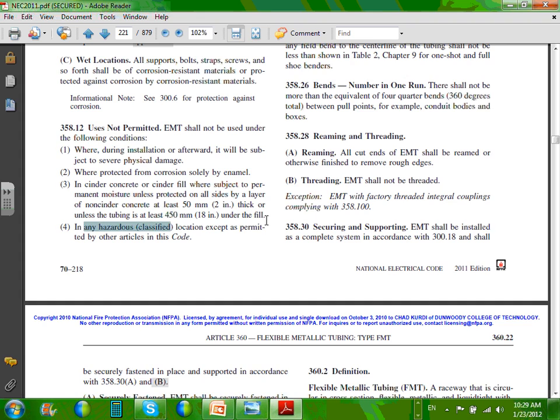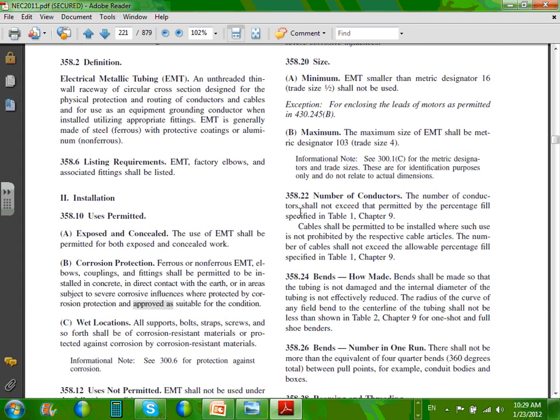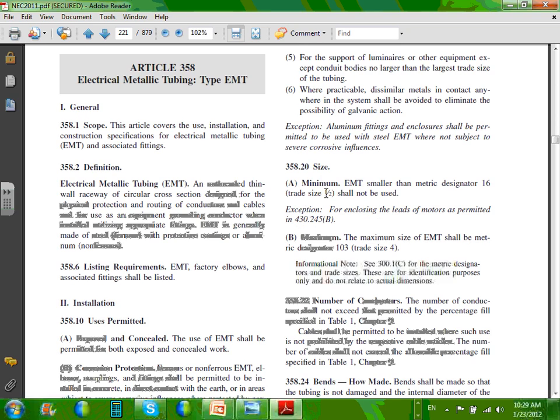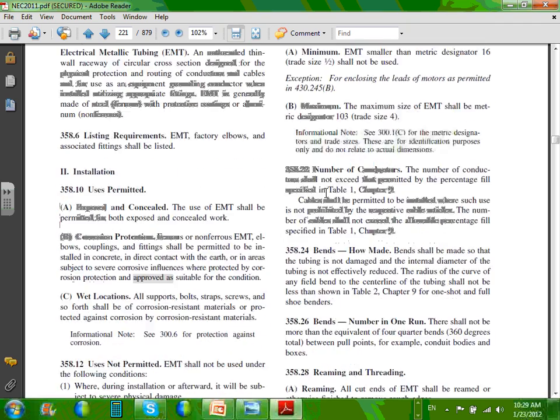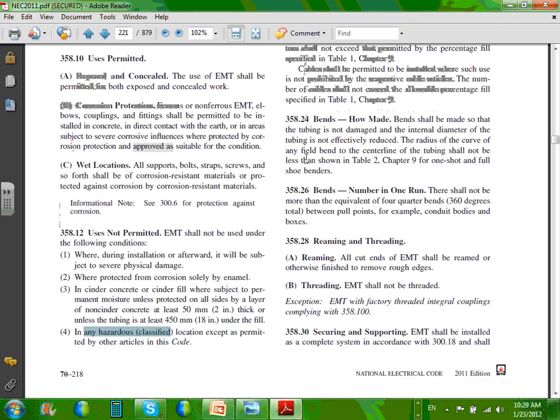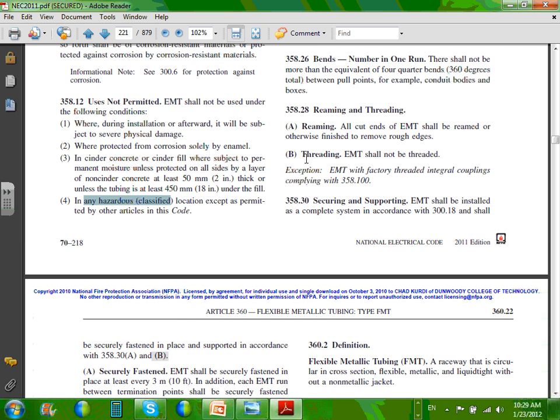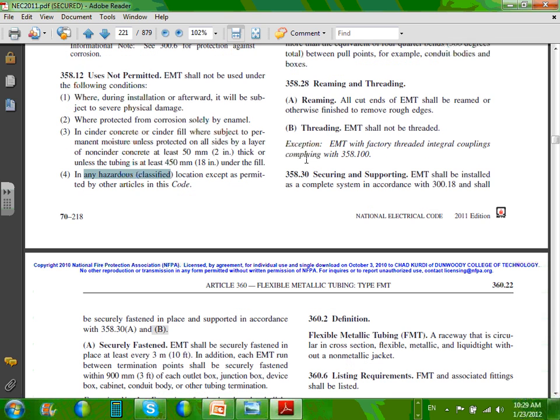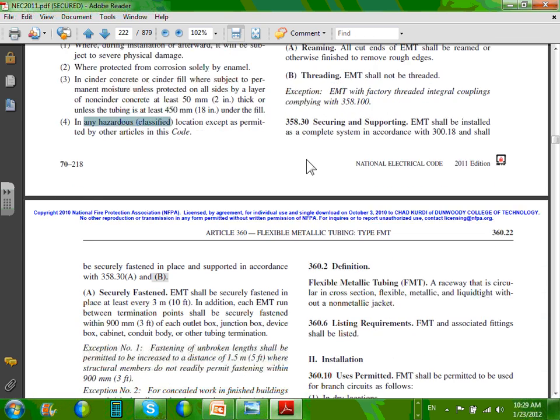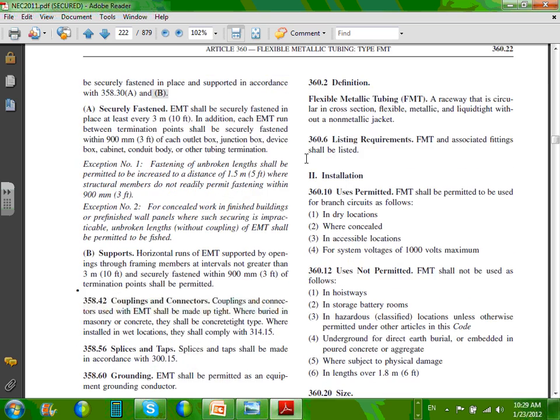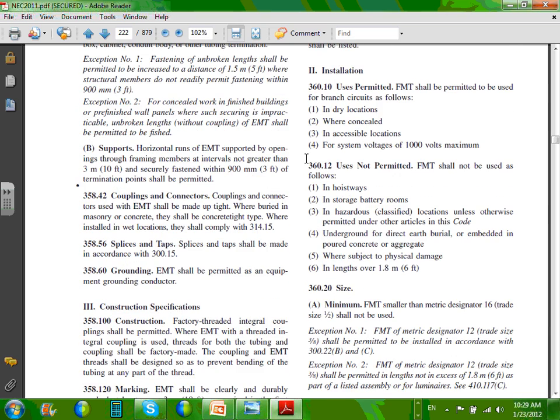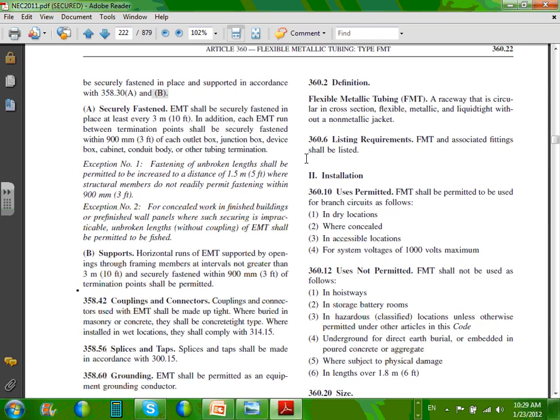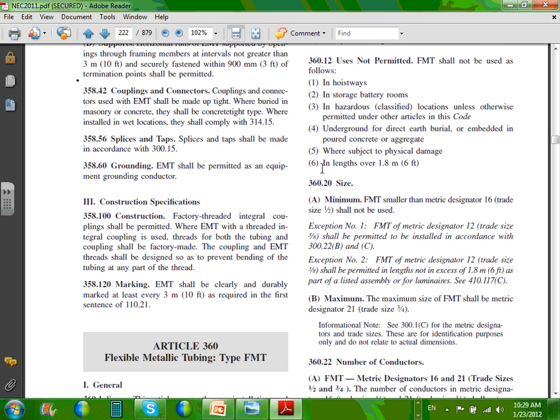In hazardous classified locations, good luck. Sizes, 1/2 inch for the most part, to 4 inch. Number of conductors, you have to go to the tables. Bends, 360 degrees. Reaming, and when you cut them, you have to ream them. No threading for this conduit. And the last thing, that's about it. For the conduit definition, EMT, sizes that they can come up with, and support. Where's my support?